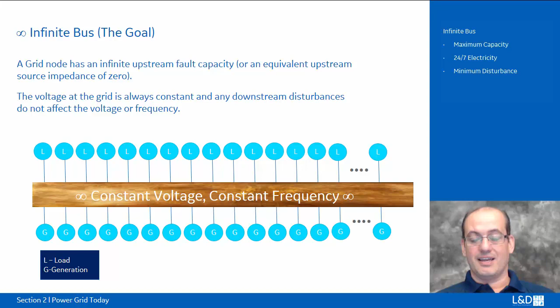You will find that there isn't one generation point in the entire grid that is setting the voltage and the frequency, what's known as isochronous. Instead, all the generators in the microgrid are adjusting to the variation and changes in the microgrid as load is added and as generation points are added to the grid. Nevertheless, the idea of the infinite bus is a perfect idea, and it is the goal of any grid managing utility.